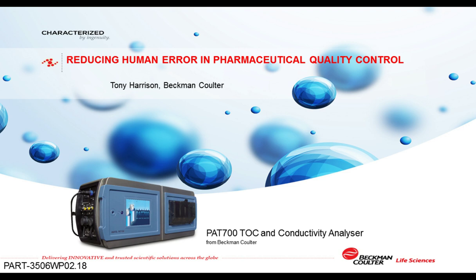You mentioned electronic records in PDF format are automatically exported from the PAT 700 TOC analyzer. Surely PDF files can be changed, so how do you ensure that the electronic record is secure? Yeah, it's a very good question, and in fact I'm challenged about that by a lot of people as I travel around the world.